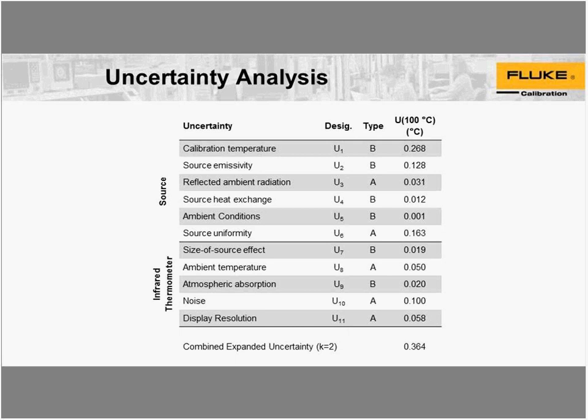I will not get deep into the uncertainty analysis for time purposes — I could probably spend another hour on this subject. This uncertainty analysis includes uncertainties listed in the ASTM standard, which are based on literature from BIPM for radiation thermometry uncertainties. This uncertainty analysis is not for a specific model, a specific source, or a specific laboratory — so don't use this in your own laboratory. Go out and compute your own uncertainties for your own calibration setup. That said, the uncertainty shown here is probably pretty typical for calibrating an infrared thermometer with a 4180 or 4181.